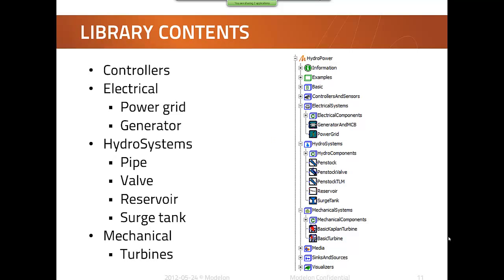Okay, so a little bit about what you can find in the library. The library content has a controller which contains special controllers for hydro power plants, which are PID based with different parameter settings dependent if the model for example is connecting on the grid or not. It contains electrical models. It contains a power grid model, so it's a dynamic grid model where it's possible to add and remove load and production units during simulation. It also contains generator models and the switch which is called MCB, main circuit breaker, which is used to connect to the grid. And it has several different hydrosystems components which you will find under hydrosystems package. So it contains discretized pipe models, valve models, reservoir models and surge tank.